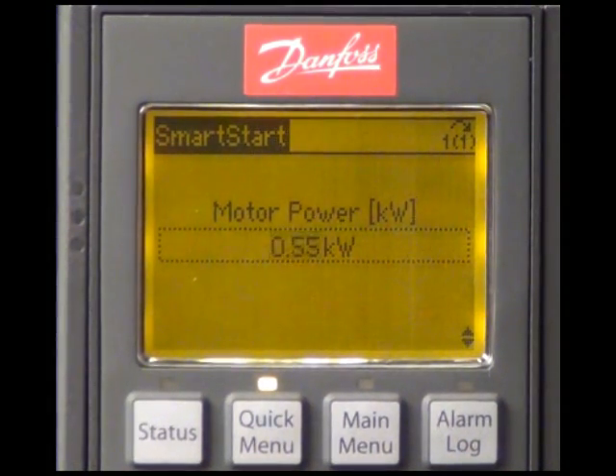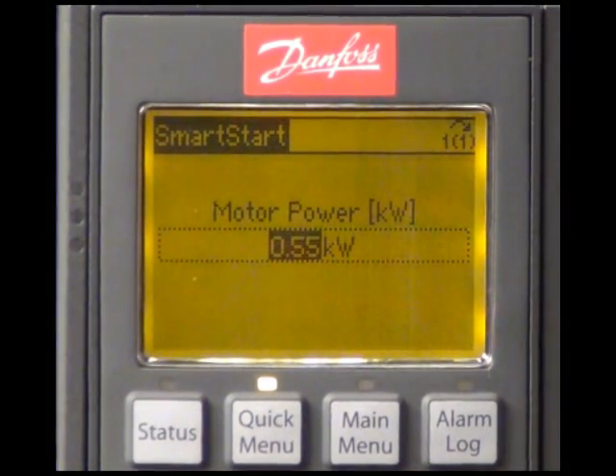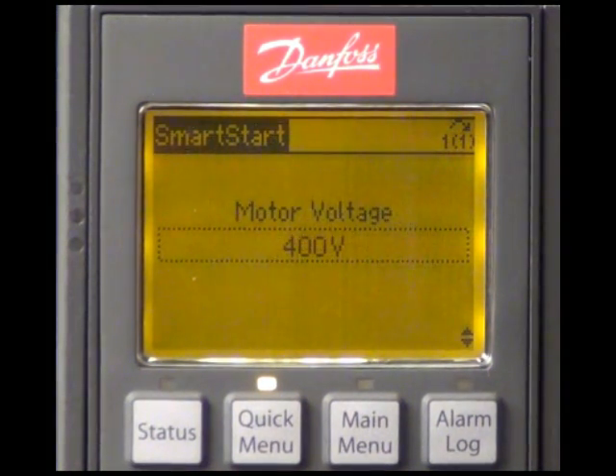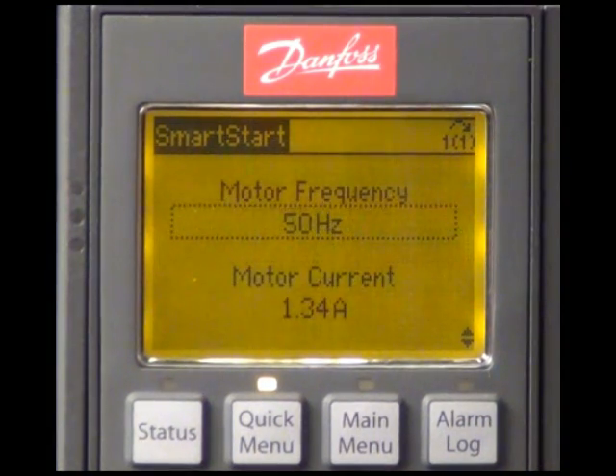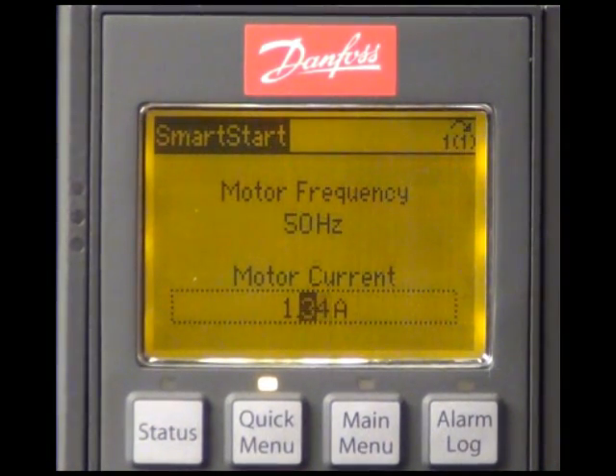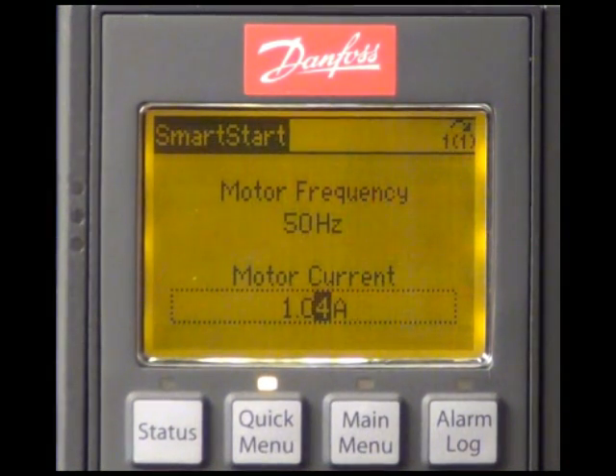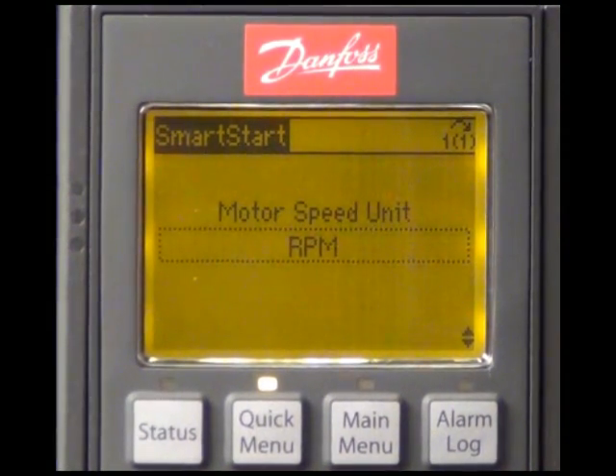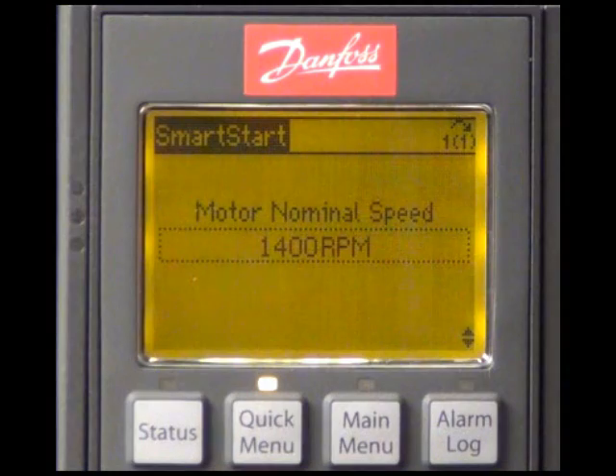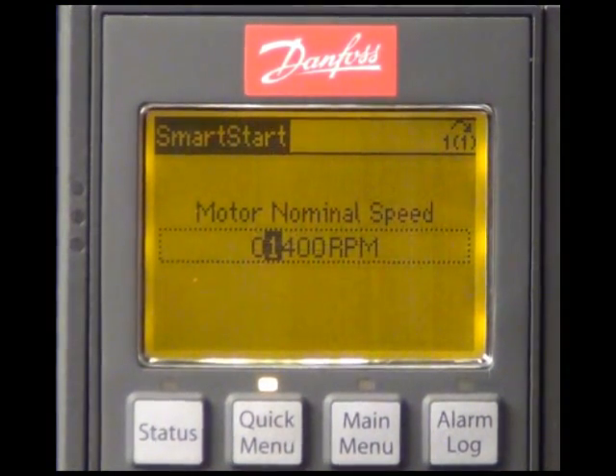We have now to enter the motor data according to the name plate. The motor power is 0.55 kilowatt, the motor voltage 400 volt, the motor frequency is 50 hertz and the motor current 1 ampere. As motor speed unit, we are selecting RPM. The motor nominal speed is 1400 RPM.